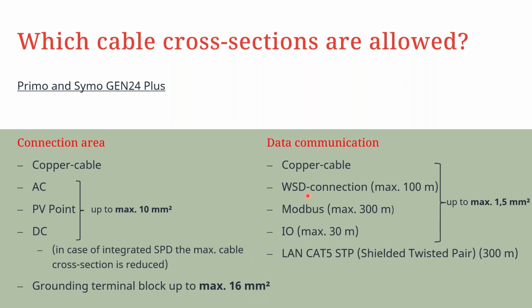We have the WSD, which is the wired shutdown. This can run a maximum of 100 meters. We have the Modbus connection, which is used for the smart meter connection. This can be run for a distance of a maximum of 300 meters. Then you have the IOs, which are the inputs and outputs from the inverter. They can go a distance of maximum 30 meters. For all these three connections, we require a maximum of 1.5 millimeter square cable cross section, which must be copper. There is also the possibility to use the LAN Cat5 shielded twisted pair cable, which can be run for a maximum of 300 meters, and this is specifically for the Modbus connection, for instance for the smart meter.